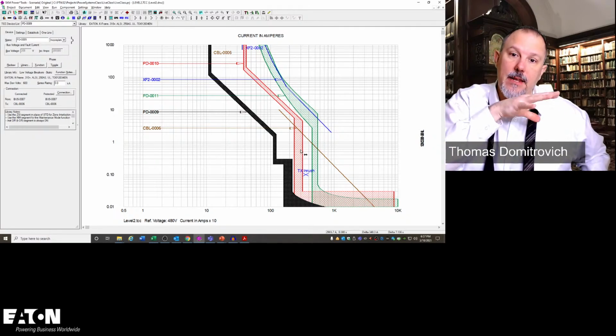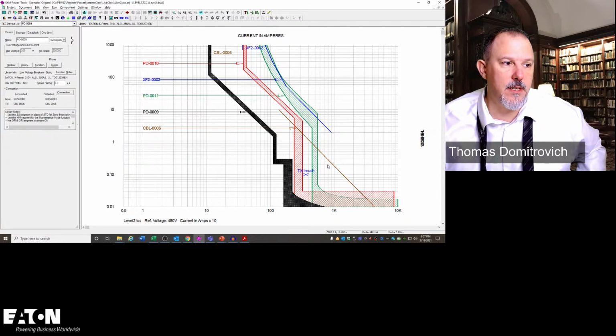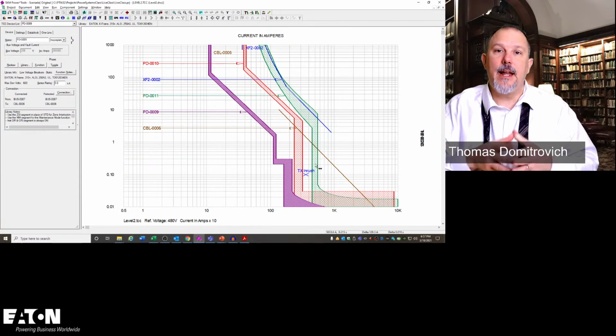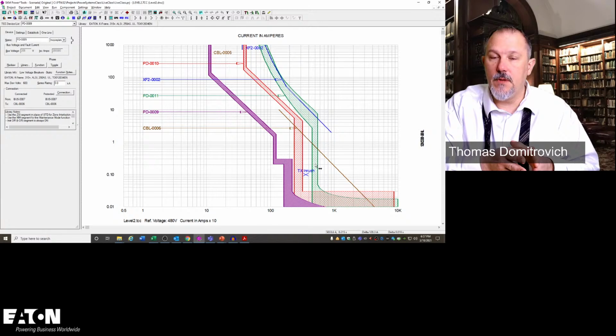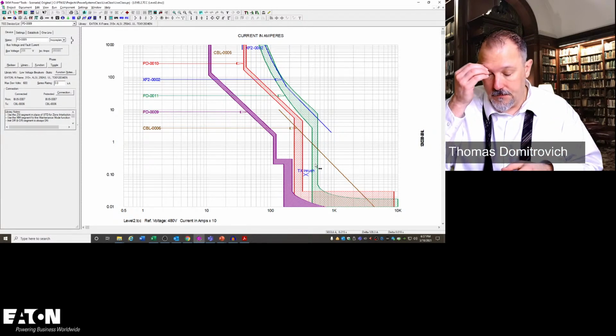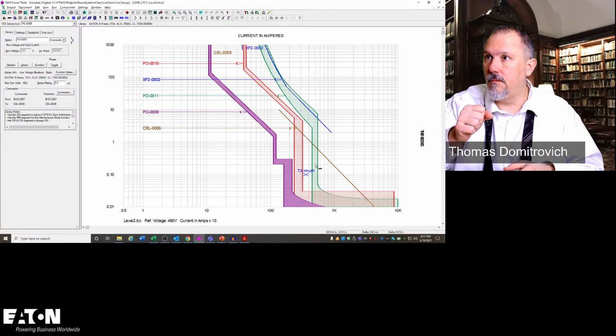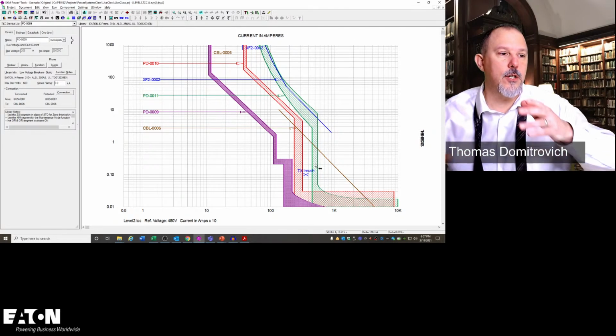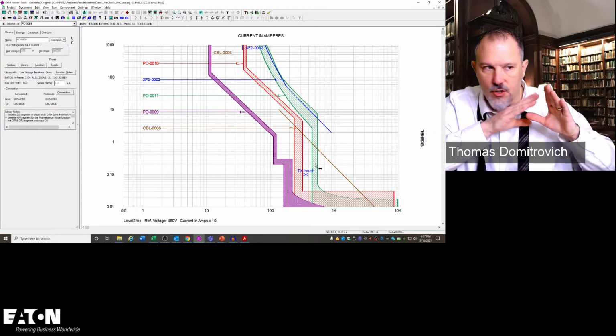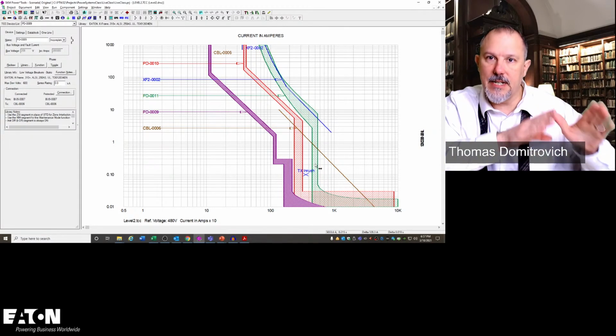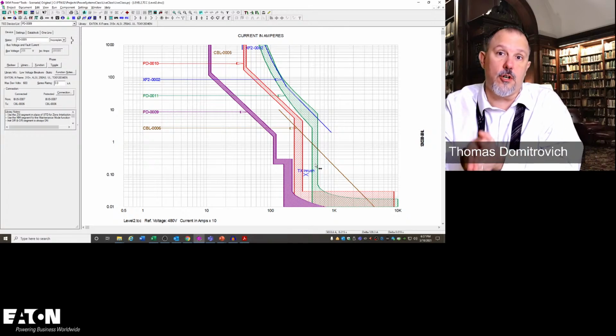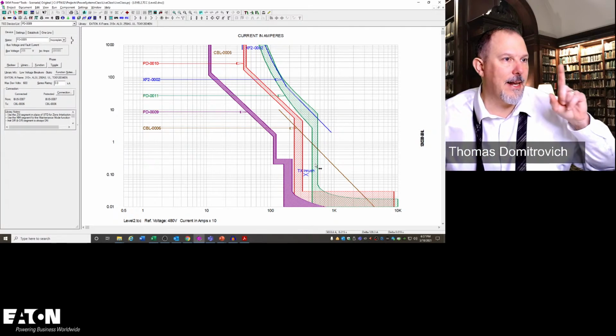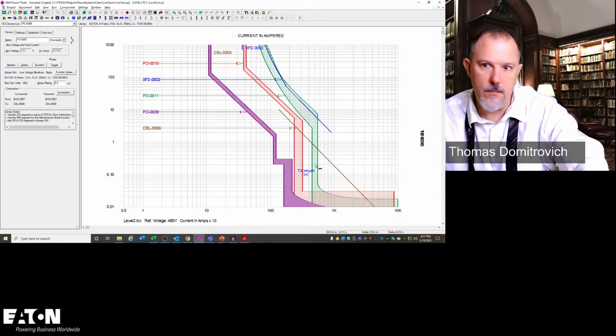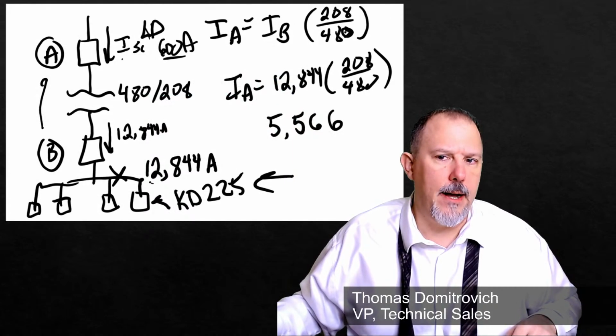I still would plot the conductor damage curve, and remember, this curve is calculated, and really what we're looking at is the damage of the insulation, not the annealing point or vaporization, right? So my breaker's going to trip fast enough, and it's thermally protecting and protecting that conductor from short circuit faults as well. So hopefully that answers the question that I got on that one. I hope I answered that question.